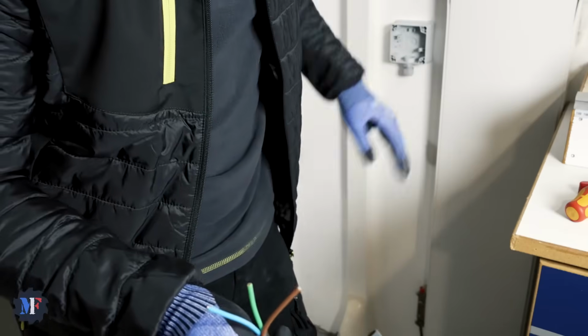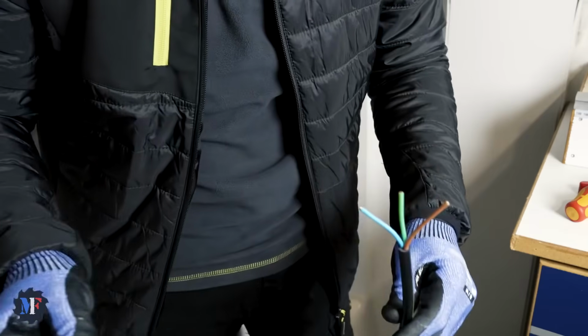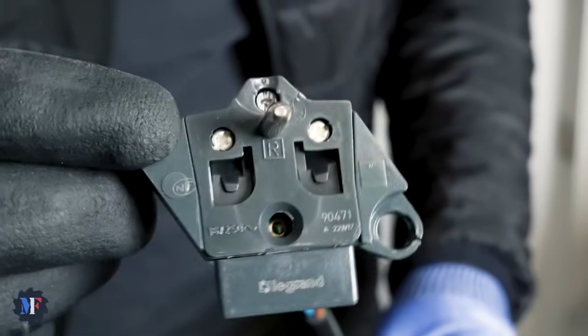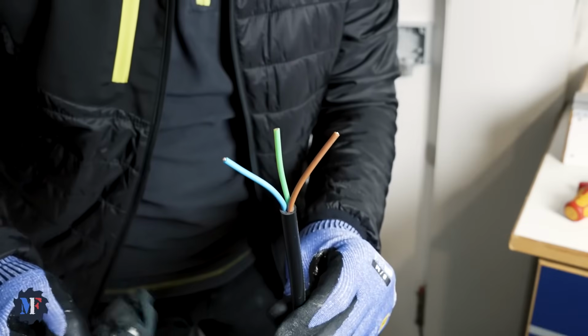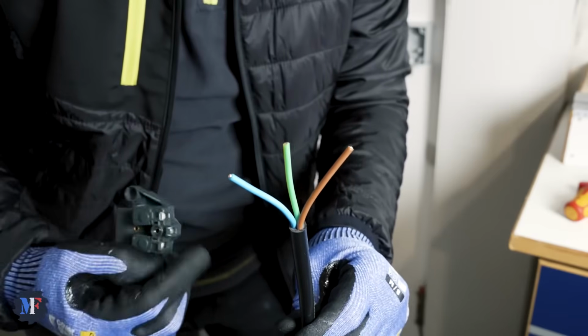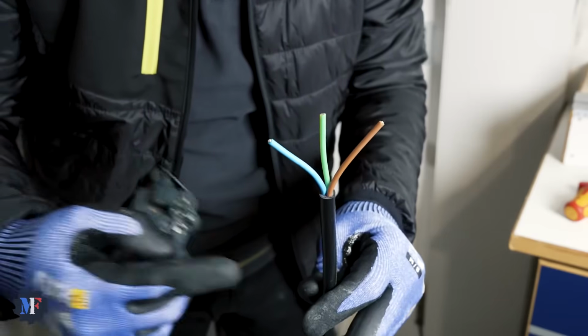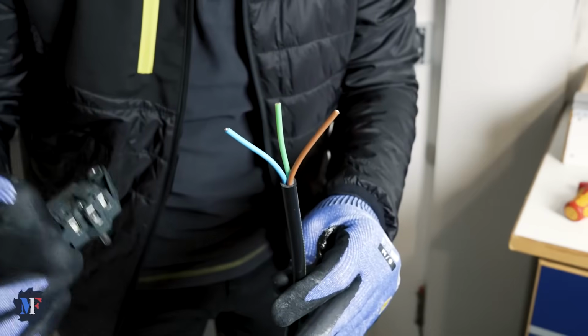The box is installed, nothing special. 4 anchors, 4 screws, the reinforced socket - you can see what it looks like. The cable is 3G 2.5, using 2.5 because I only have 50 centimeters of cable. If you have long distances, 30, 40, or even 50 meters, use 6mm2.